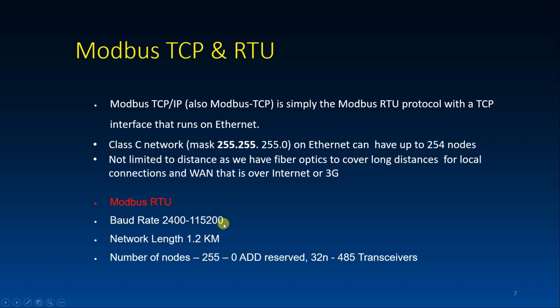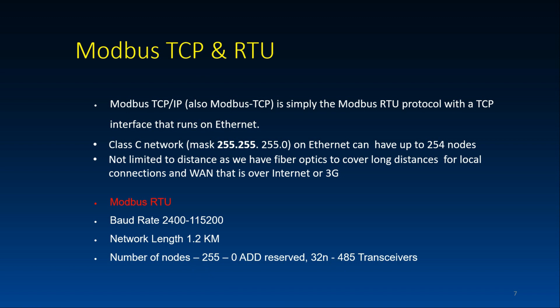For Modbus RTU, there are parameters to configure depending on the controller, such as baud rate and parity bit. The maximum cable length is 1.2 kilometers, though this also depends on the transmission speed. The maximum number of nodes is 255, but on each segment only 32 devices can be used, as this is limited by the RS-485 transceivers.